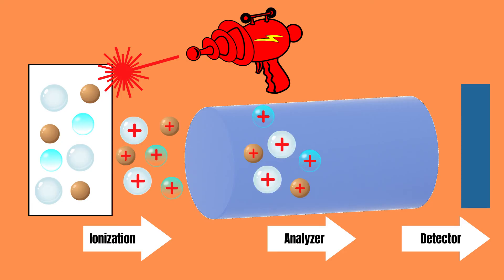Then the mass analyzer separates them based on their mass to charge ratio or m to z ratio. In the case of MALDI-TOF, the sample gets separated based on the time it takes its constituent parts to fly through the time of flight or drift region of the detector. Since the sample has been ionized, it can be accelerated by a high voltage current and fly through the tube before it strikes the detector. The time needed for each molecule to reach the detector depends on its mass, meaning that smaller molecules will reach the detector faster than larger ones.